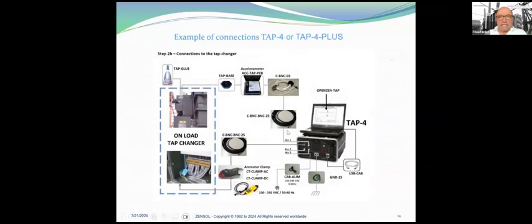So here you have an example of connections of TAP-4 or TAP-4-PLUS. First of all, you have to choose the spot where you are going to install your accelerometer. We use glue. Here, this is a tap base where the accelerometer is screwed. Here, it's a specific cable which converts to BNC, which is a standard cable. And then it's exactly the same for the current. Here, you can see an AC current clamp, or we also use a DC current clamp. It depends on your tap changer.